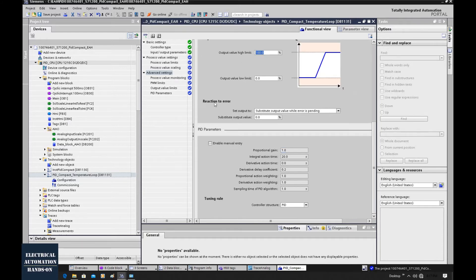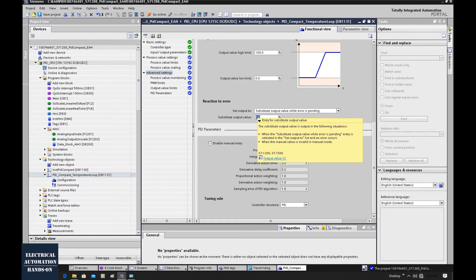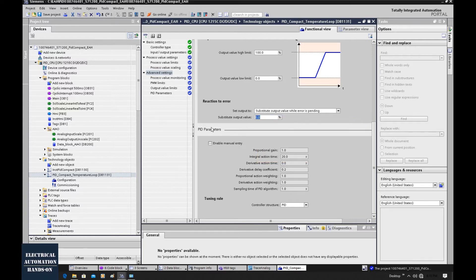This setting is very important: Reaction to Error. When the PID control loop gets something wrong, this determines the behavior of the output value. Usually we will set a value that is safe for your system. For example, if your valve being totally closed is safe, you can set 0. But in some special cases, maybe having the valve 100% open is safe for your process — in that case, you can set 100 here. By default it is 0.